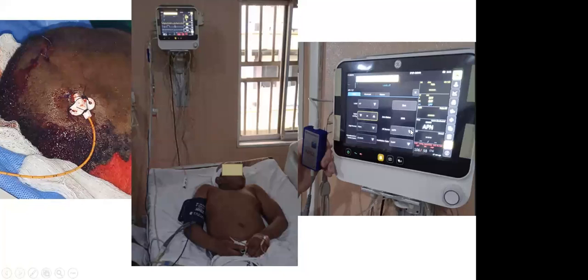Then this comes up. When this comes up, the ICP is clicked, and the MPS2 has a button where the zeroing is done. While the thumb is placed on the button on the MPS2 to zero, the point on this dialog box for zeroing is clicked, and it naturally zeros. Thereafter, the dialog box that displays is closed. Then at this point, with the three dots, the intracranial pressure value comes up. So that's using the patient monitor.